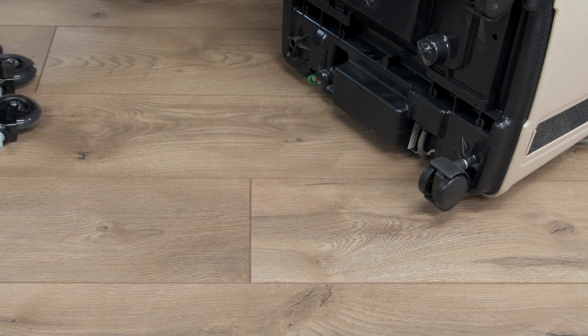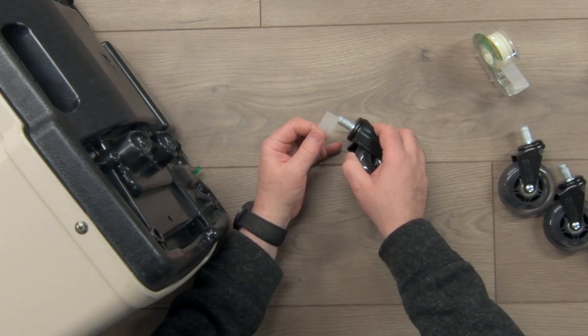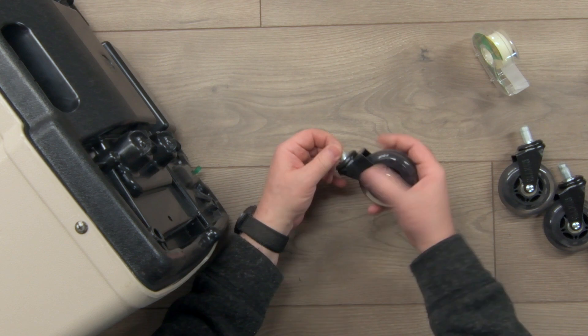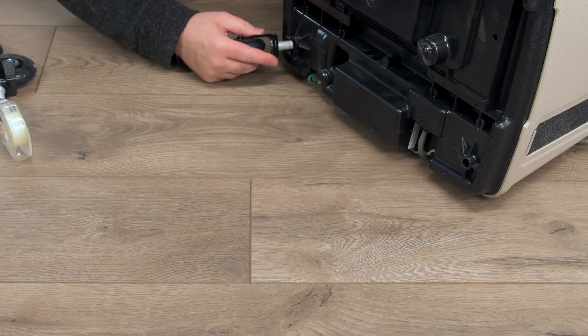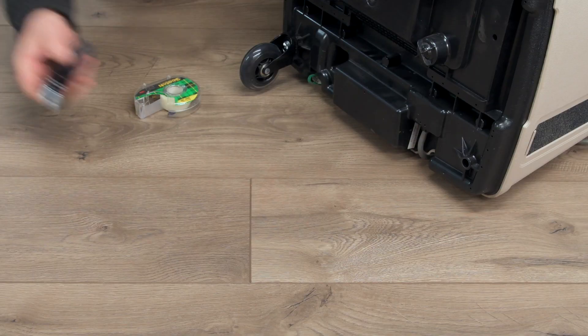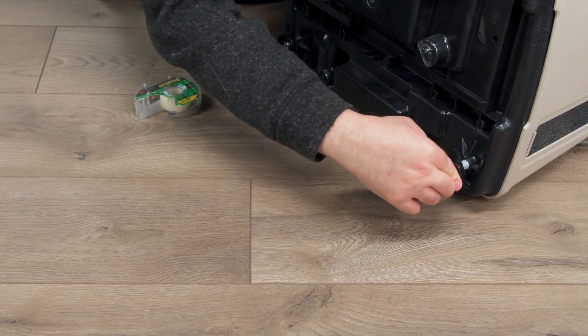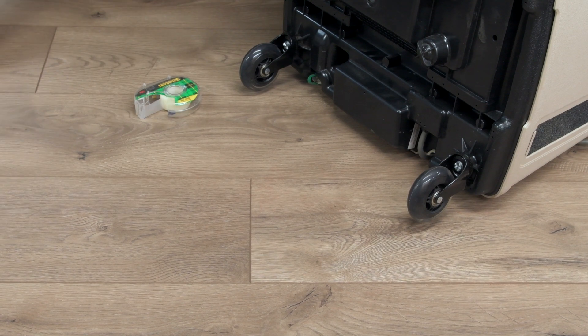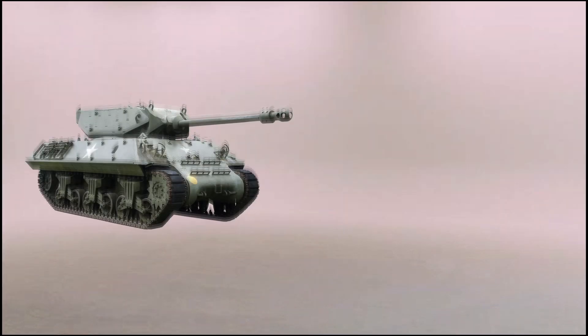The casters on this unit come out very easily. The new casters had a looser fit, so I wrapped the stems in a bit of tape to prevent the wheels from dropping out of the cabinet. Hold on to the old ones, though, so if you have to have the concentrator replaced, you can pop them back in. An added benefit of replacing the casters is that it has transformed this very heavy machine into one that's now incredibly easy to move.